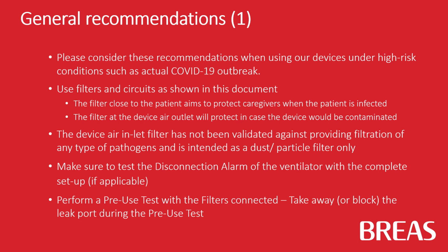The filter close to the patient aims to protect caregivers when the patient is infected. The filter at the device air outlet will protect in case the device would be contaminated. The device air inlet filter has not been validated against providing filtration of any type of pathogens and is intended as a dust or particle filter only.